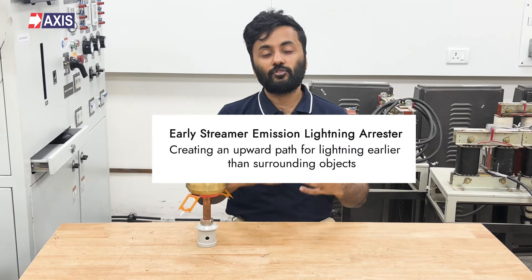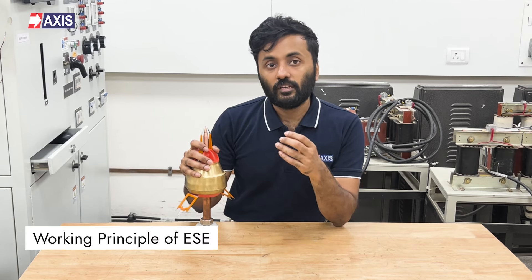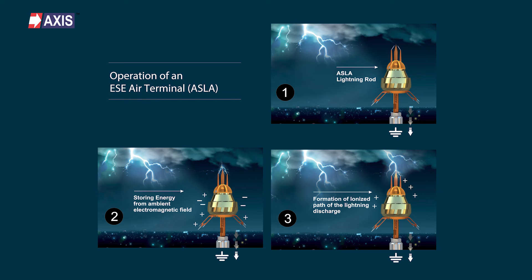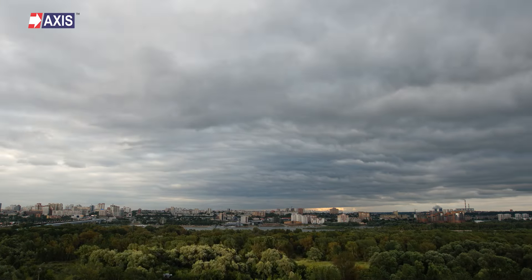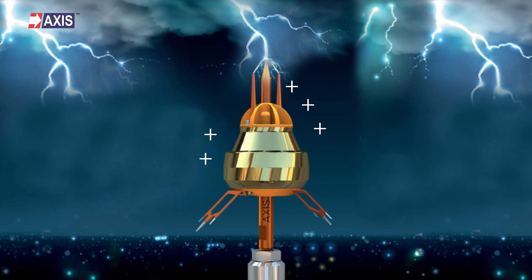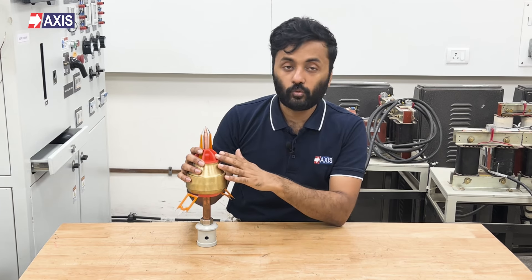Put together, an early streamer emission lightning arrestor creates an upward path for lightning earlier than surrounding objects, aiming to protect you from direct lightning strikes. The emission from this arrestor is generated by storing energy from the ambient electromagnetic field at the time of lightning events. The ESE device has a tip called an air terminal. In normal conditions, this air terminal is inactive. When a charged cloud approaches, it creates a strong electric field in the area. The ESE device detects this change and sends high-voltage pulses from its tip, turning the air around the tip into ionized air, which conducts electricity better than normal air. This ionized air creates a path that guides any lightning strike safely to the ground through the ESC device.